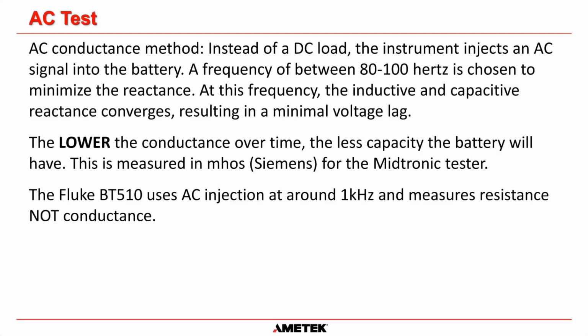And the difference between the AC test and the DC test is, for the AC test for the Midtronics, they are measuring mhos or Siemens or conductance, okay? And the lower the conductance over time, in other words, the lower the battery has the ability to conduct, then the less capacity the battery will have. So it's the inverse of the DC load test. So remember, for the DC load test, the higher the resistance, the less capacity we have. But for conductance, the lower the conductance, the less capacity the battery will have over time.